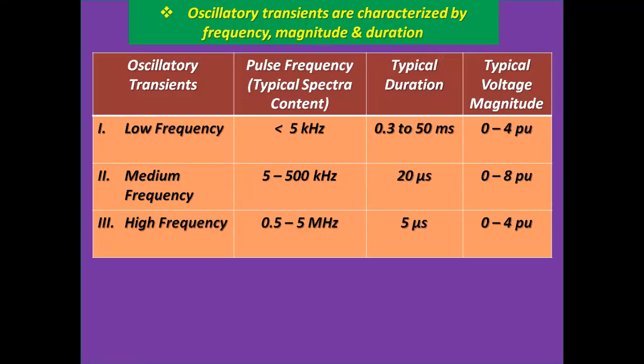Let's start with oscillatory transients, which are characterized by frequency, magnitude, and duration. There are three types of frequencies. One is low frequency, whose pulse frequency is less than 5 kilohertz, and typical duration is 0.3 to 50 milliseconds, and typical voltage magnitude is 0 to 4 per unit.